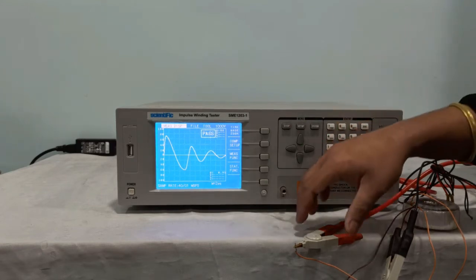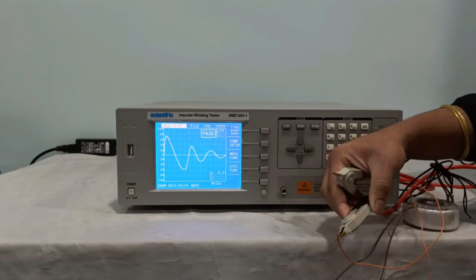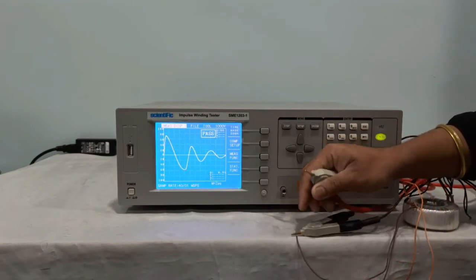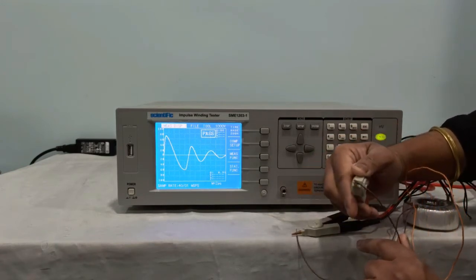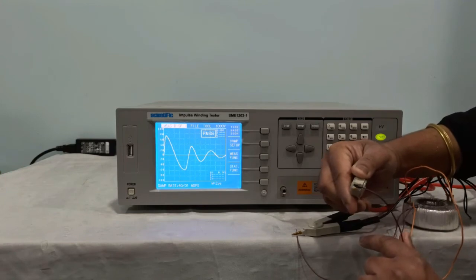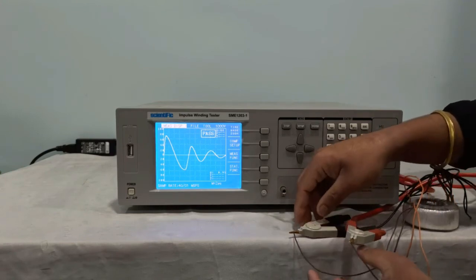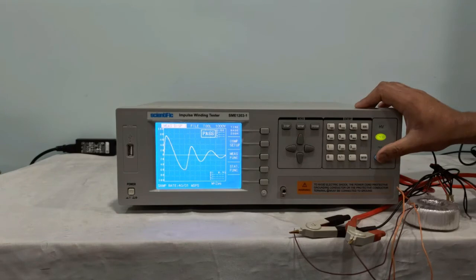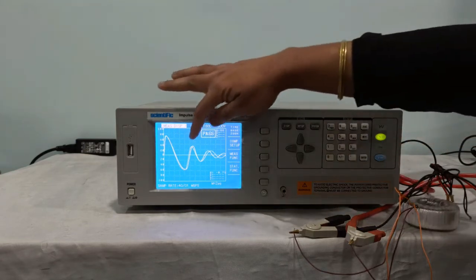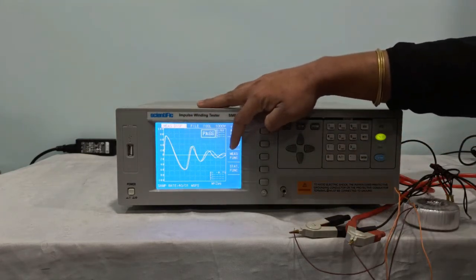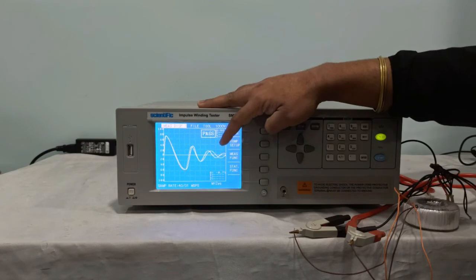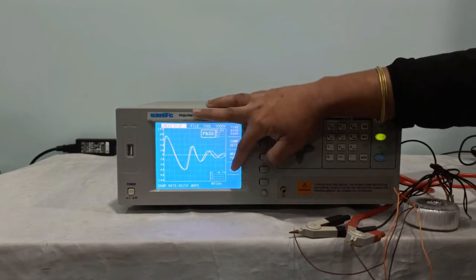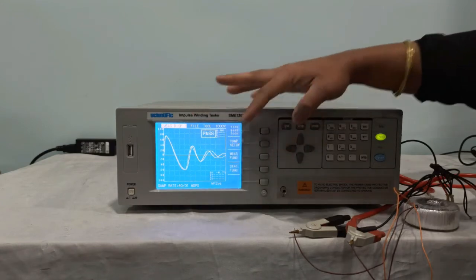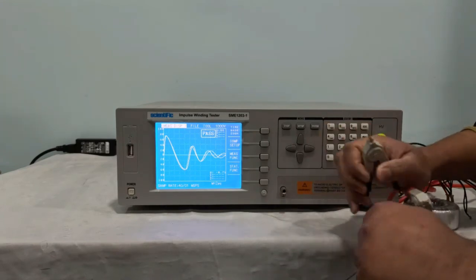Now we'll change the DUT. We'll connect it to the other winding of the transformer. So the master we have created from one winding and we are testing it on the other winding. We'll just press start. You can find a deviation on the screen, but this winding has also passed because the tolerance is 0.7%. We'll try with different windings.